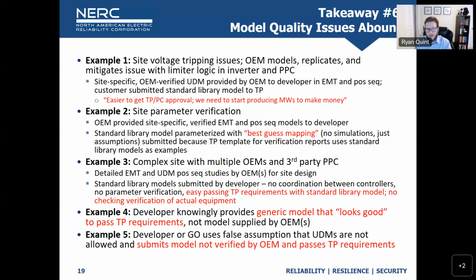Example 1: the plant was having voltage tripping issues. The OEM comes in, models the whole thing in detail, and replicates the tripping with detailed limiter logic in the inverter and plant controller. That OEM provides a verified site-specific user-defined model to the developer, both in EMT and positive sequence. But the interconnection customer, the developer, turns around and submits a standard library model to the TP instead, because it's much easier to get TP/PC approval and they just need to start making megawatts—that's how they make money. So the model becomes irrelevant.